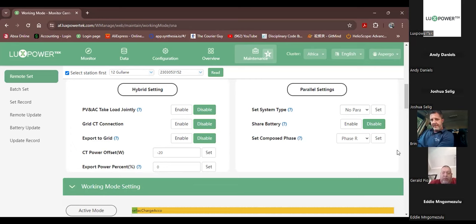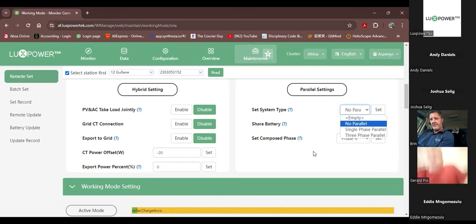On the parallel setting side, once again, exactly the same. You can choose a single phase parallel or a 3-phase parallel. Now, remember that you have to refer to the manual that comes with the machine to see what the CAN bus node must be set at. When I refer to the CAN bus node, I'm talking about the dip switches under the machine. Under the machine, you will have a little blue or red block with two dip switches on it. That's typically your 120 ohm resistor.